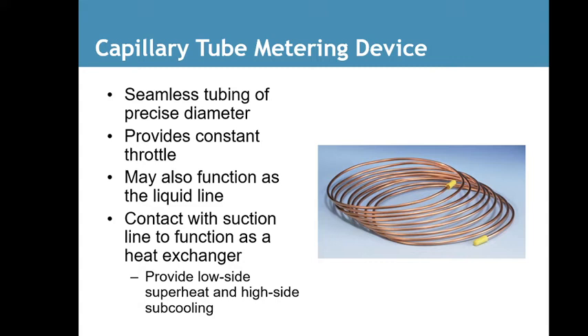The problem with this tube, though, is it plugs very easily. So any debris that gets in this line at all will cause this tube to plug. The good thing is you might have 8 of these tubes on an evap coil in an attic or in the air handler outside or wherever it happens to be. So if one gets clogged, you still have 7 others that will work, and you might not know that one part of the coil is not working until you touch that coil with your hand. You feel a spot on that coil that's not as cold as the rest of it. That capillary tube probably has a problem.